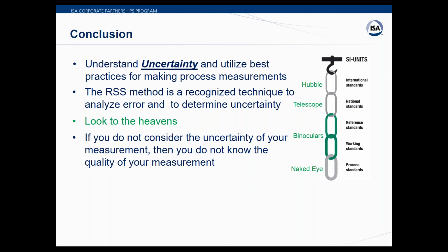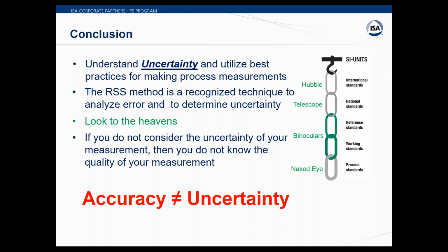So bottom line is if you do not consider uncertainty when making measurements, then you just don't know the quality of your measurement. So if you think back to Roy's demo where the measurement was one-to-one, they both looked good. The curve came out the same. That had the same slope, and it barely passed at zero and was almost spot on at span. But the quality of the measurement was very suspect, and you don't know at that zero if you really were in a pass or fail condition because you weren't using the appropriate standard.